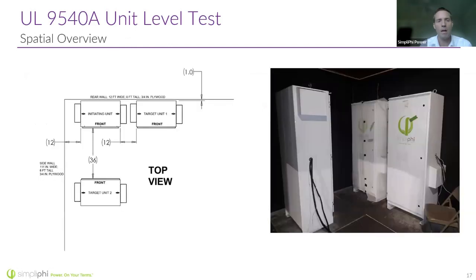Here's what the testing setup looks like. We have the spacing dimensions. We have only 12 inches between those individual battery cabinets. Those cabinets are then, to meet the NFPA code, 36 inches in front. So that's the spacing, as close as we could get. And we've got, again, like I said, 136.8 kilowatt hours of battery that's there. They are surrounded by a 3/4 inch plywood wall, and the room that they're being tested in is 12 feet wide. And I think in this particular setup, we're looking at an 8-foot tall ceiling as well.